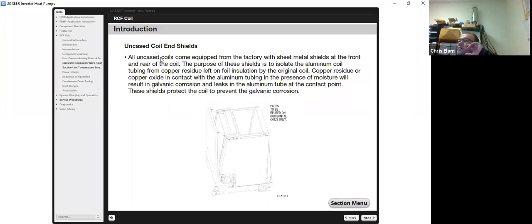So if you hear the uncased coil end shields, on the side here, all uncased coils come equipped from the factory with sheet metal shields at the front and rear of the coil. The purpose of these shields is to isolate the aluminum coil tubing from copper residue left on coil insulation by the original coil, or any copper that could have been there.